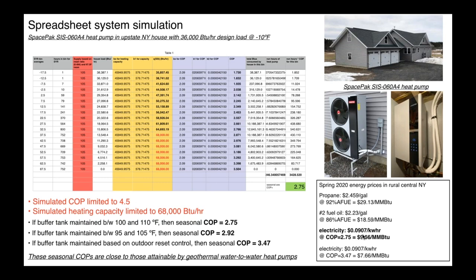So we're on the order of half the price of fuel oil for the energy coming from this air source heat pump. And if we went to a full outdoor reset scenario where we averaged 3.47 on our COP, you can see we're down to a little under $8. Again, I'm looking at what the utility costs are and comparing it to what the simulated, and I would say reasonably accurate, simulation of the heat pump and the building would be. And we're seeing very competitive operating costs in relation to other fuels.